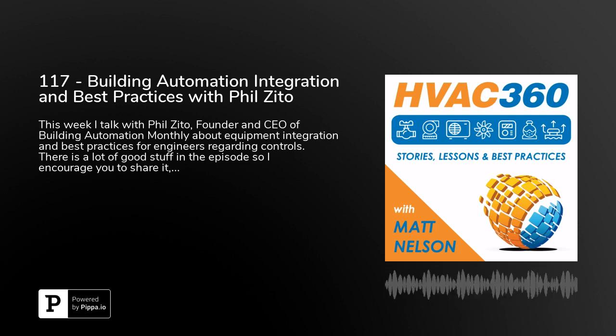Thanks for pulling me back, I can go pretty deep down the tech rabbit hole fast. At a high level, if I'm an engineer, I want to know what communication interface options are available, and understand the main protocol of the BMS system I'm using. So if its main protocols are BACnet MSTP and BACnet IP, I want to make sure my equipment has an MSTP or IP interface. That's the easy way, and then it's up to the controls contractor to ask for the points list and stuff like that.